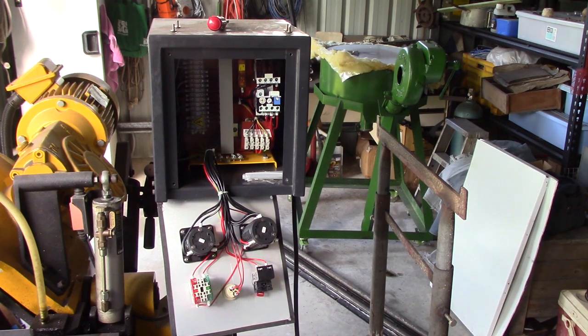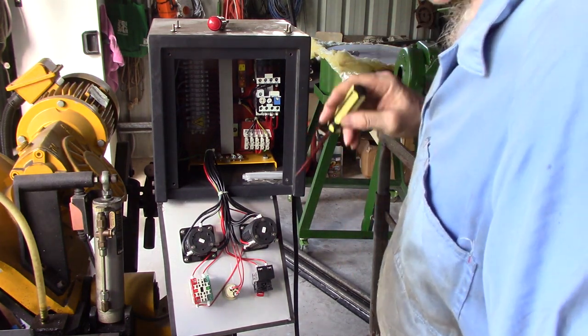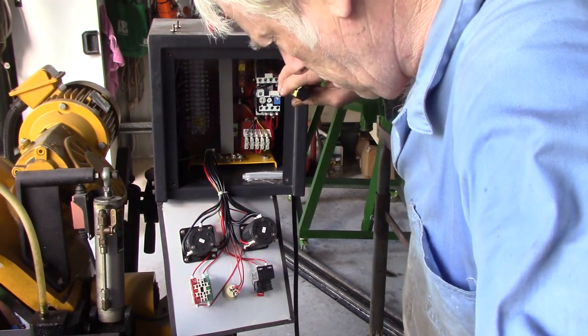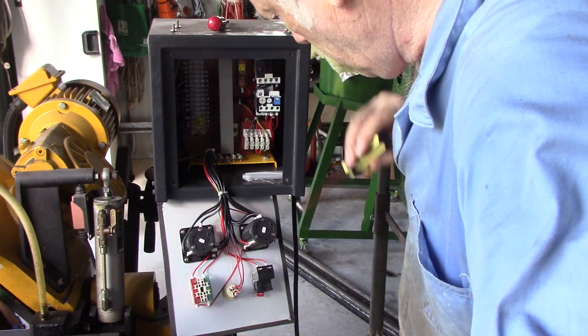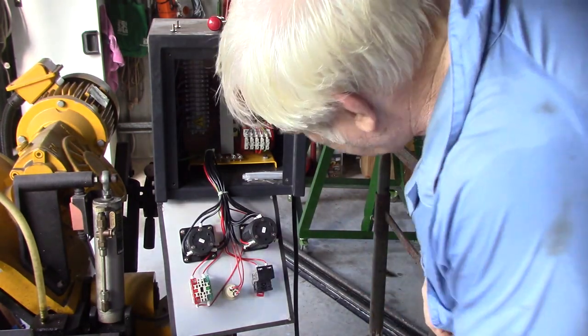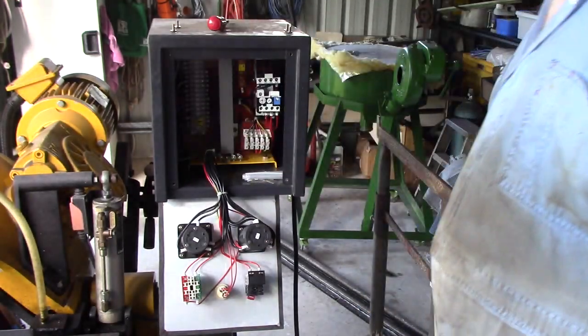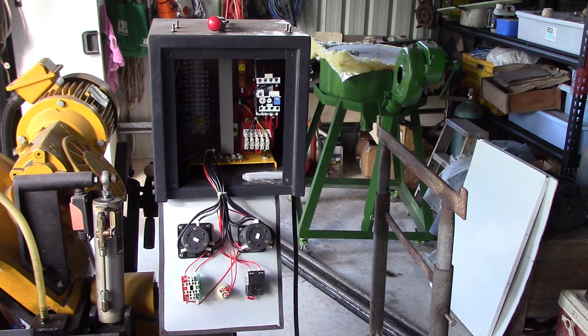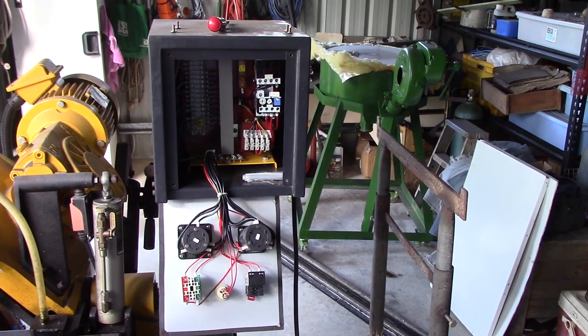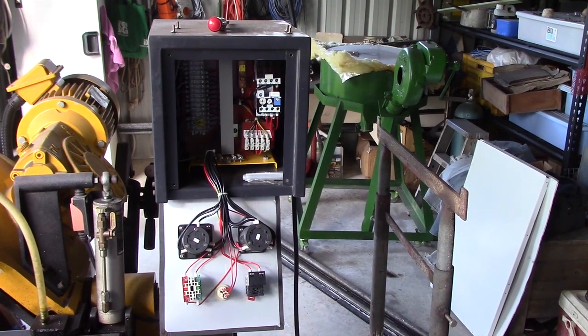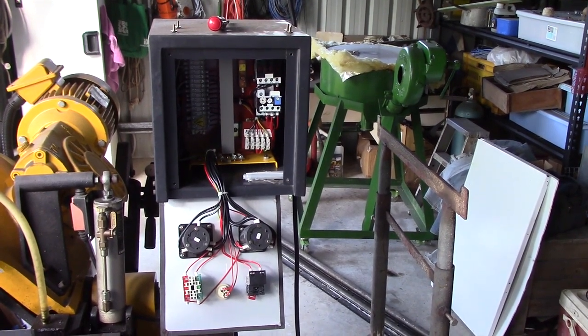I've got the box live now. Don't do this at home unless you're comfortable and familiar with working around mains voltages. If I trip the solenoid manually with an insulated screwdriver, then it all works. It seems to me that the solenoid is not working. I'll take the outside box off so I can get in and have a really good look at it. And of course, before I start messing around taking the outside box off where I'm likely to inadvertently touch things, I am going to disconnect the power.